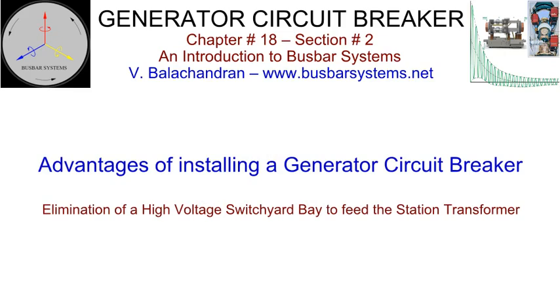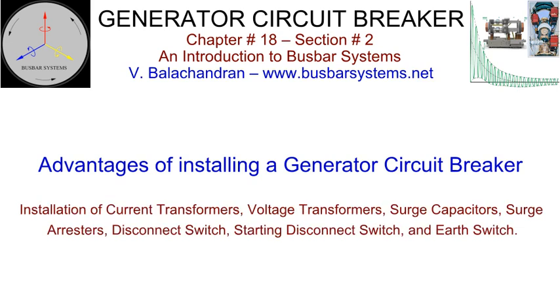There are several advantages of installing a generator circuit breaker. It may be economical to install a generator circuit breaker than to have an additional switch yard bay with a startup transformer and associated high-voltage and medium-voltage switchgear. It is possible to install several electrical accessories on either side of the generator circuit breaker for metering, protection, and control, such as current transformers, voltage transformers, surge arresters, surge capacitors, starting disconnect switch, and shorting and earthing switches. These accessories will form an integral part of a generator circuit breaker in a common housing.